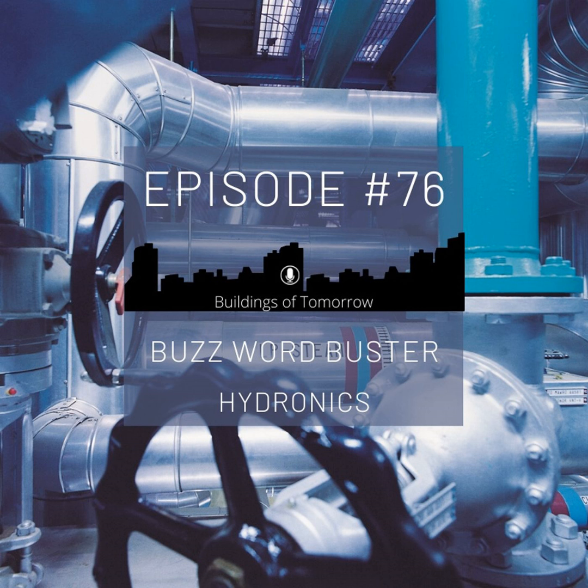And then the third component is that in these PICVs, pressure independent control valves, we also have the possibility to limit the maximum flow, and by that we are already one big step in the direction of hydronic balancing. Perfect. And you mentioned the maximum flow. That's actually the next word we had on the list, Vmax.